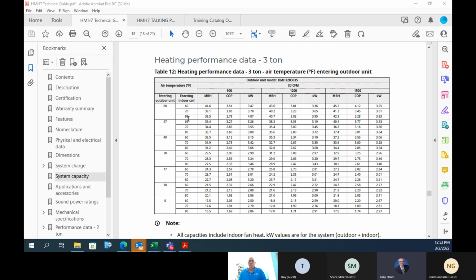And so at 47 degrees with 70 degree entering indoor coil air temperature, you see that you have a capacity at 1200 CFM of 35,400 BTUs. That's pretty stout for a 3-ton unit, isn't it? It is. And furthermore, if you can increase that airflow to 1500 CFM, a little bit more airflow, you get 36,300 out of that unit. But let's just look at median airflow at 1200 CFM.